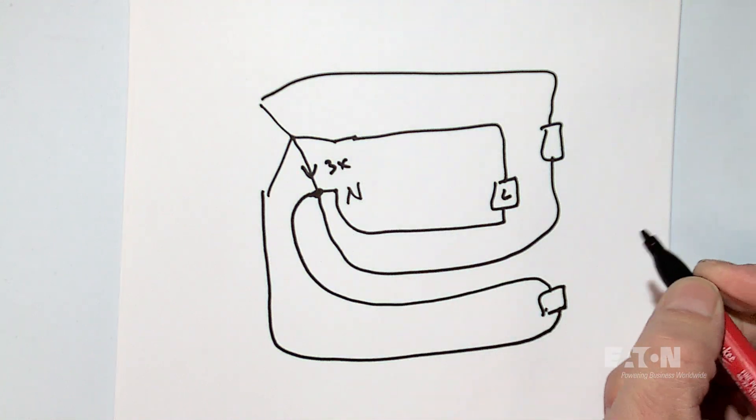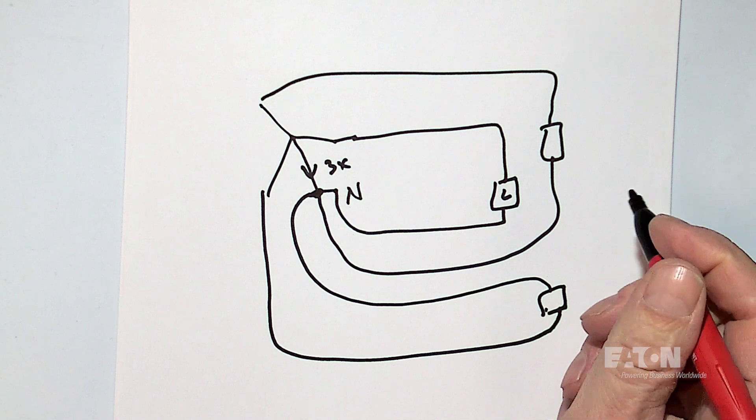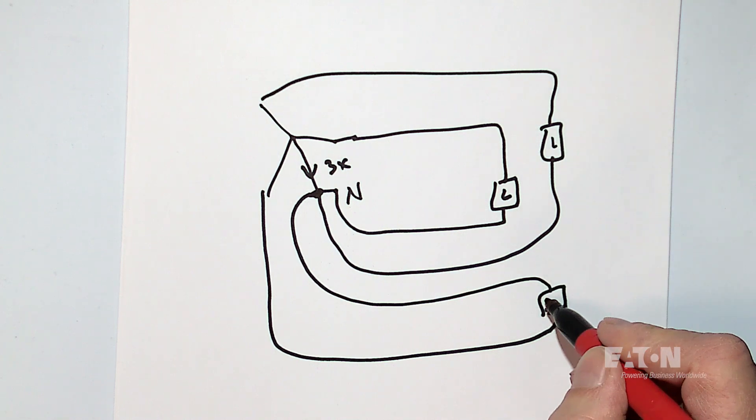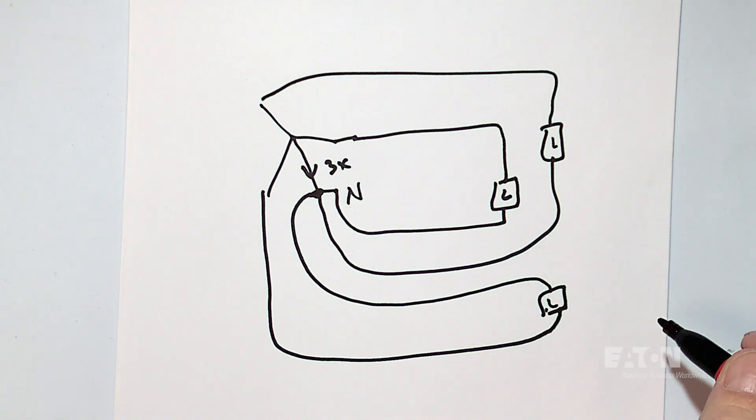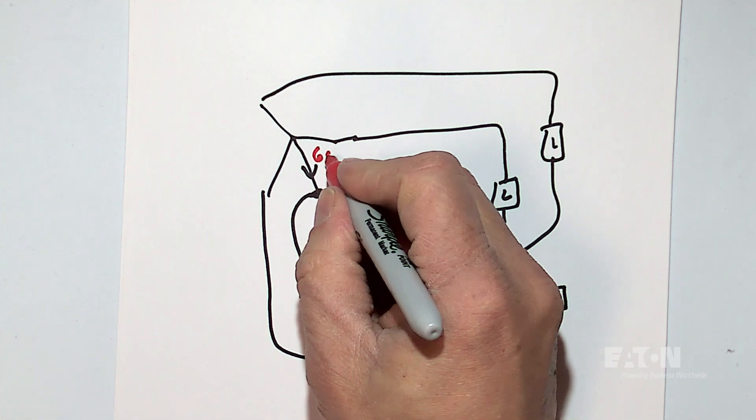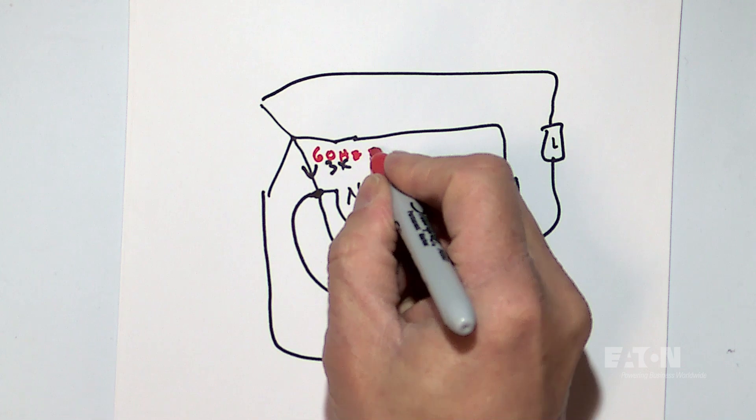So in this part here, we could have 3x the third harmonic current. But again, if my phase A, my phase B, and my phase C loads are all equal, my 60 hertz part here, 60 hertz equals zero.